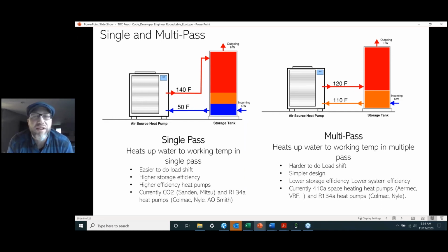It really comes down to the kind of equipment and the cycle. I don't think single pass is more expensive than multi-pass. The 134A machines out there, Nyle, Colmac, Mitsubishi, and Sanden, can all do single pass, and some of those devices can also do multi-pass. The costs really come out of the heat pump, the storage, and the piping that connects it. There might be a little more piping, but I don't think you'd see a lot of price difference between the two, outside of the specific heat pump technology, since we've seen a range in cost. But I think you're going to get a lot more out of the single pass.